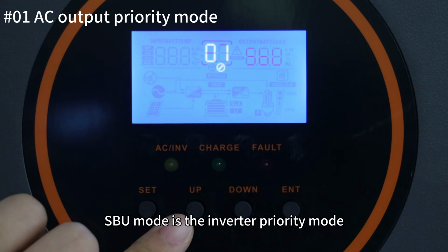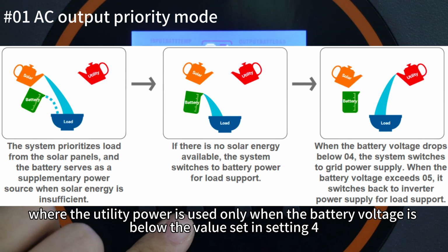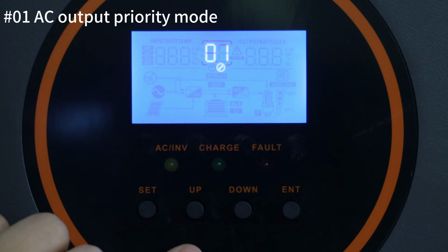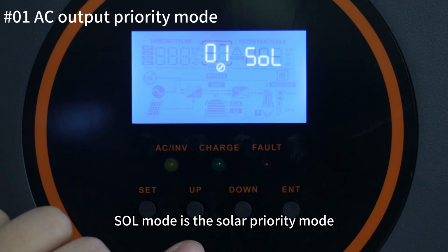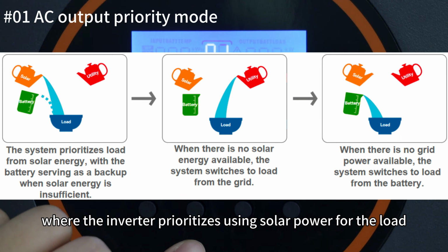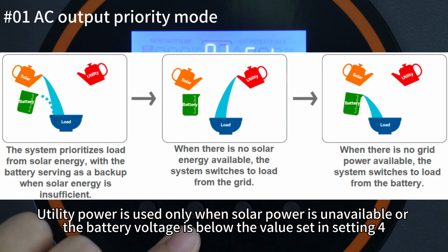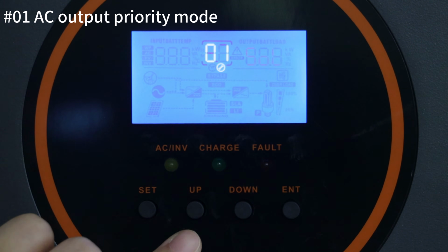SBU mode is the inverter priority mode, where the utility power is used only when the battery voltage is below the value set in setting 4. SOL mode is the solar priority mode, where the inverter prioritizes using solar power for the load. Utility power is used only when solar power is unavailable or the battery voltage is below the value set in setting 4.